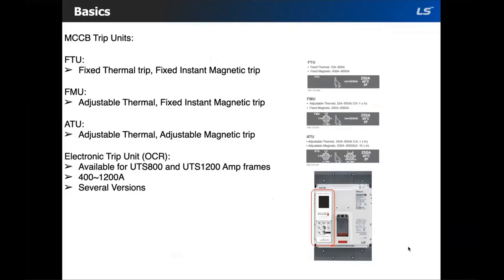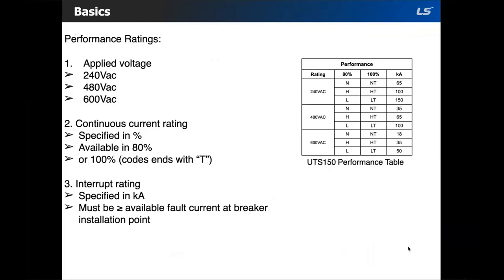For the UTS 800 and 1200 amp frames, there are various electronic trip units that we call OCRs. The OCR types will be covered in more detail in the accessory sections. Before we close out the basic section, there needs to be a clear understanding of performance rating of MCCBs and how they are represented in the LS literature. There are a couple of factors that need to be considered when deciding which performance rating is required of your breaker. First, the system's applied voltage needs to be identified.